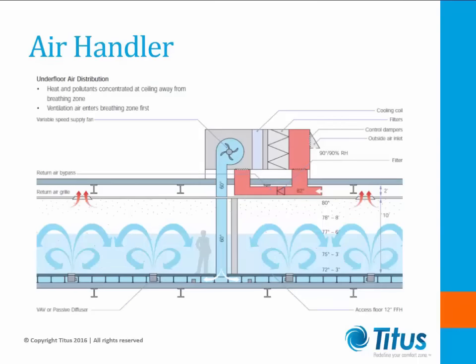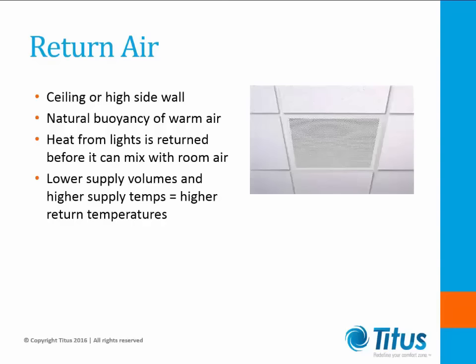So where does the supply air come from? It comes from an air handler, which could be located in an equipment room inside the building or on the roof. Cold supply air will be ducted into the UFAD plenum and return air will be ducted back to the air handler from the ceiling. In UFAD systems it's preferable to locate return grills in the ceiling or high side wall, taking advantage of the natural buoyancy of warm air to rise and exit the room. The higher supply air temperatures and lower supply air volumes in UFAD systems result in higher return air temperatures than those of conventional overhead systems.